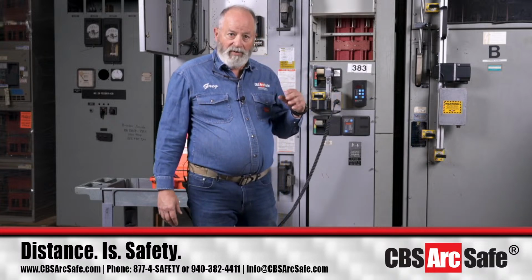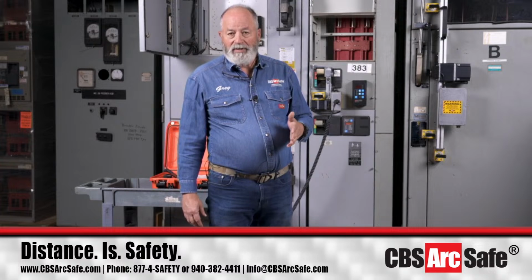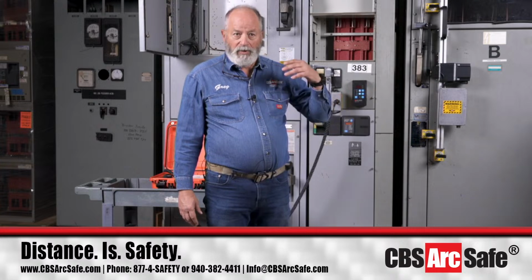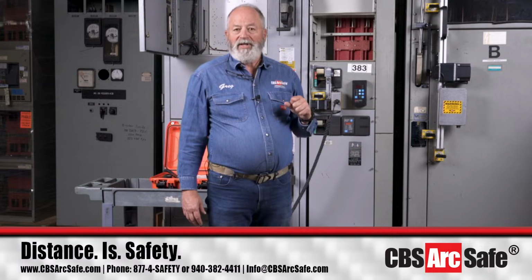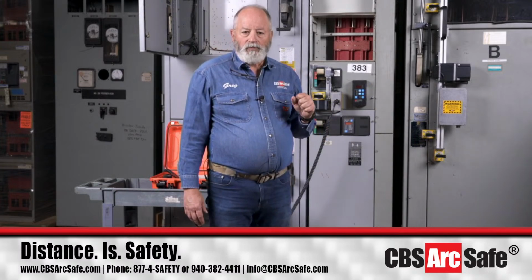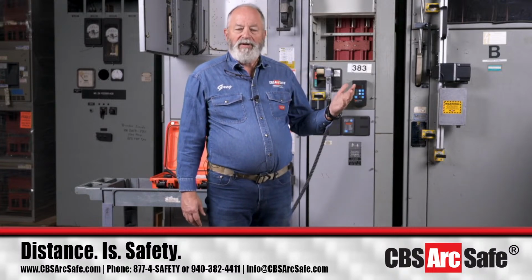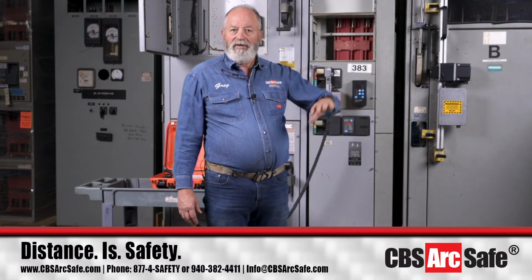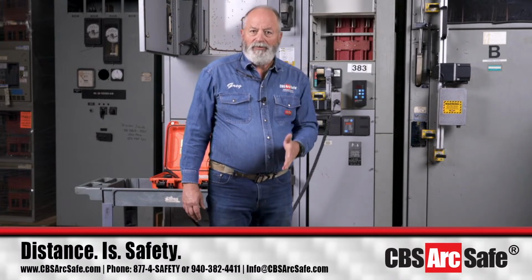And so we have things that can go for just the Allen Bradley, whether you want the single application, ABL1, ABL3 series type of thing, or whether you want our RSA 71 series, okay? Sometimes you may run into a door configuration, and this is important, where bolts will interfere with the mounting because you've bought something made by an OEM afterwards that put an Allen Bradley contactor in the door and slapped their thing on the face. And so you'll need the RSA instead of the ABL3, okay?